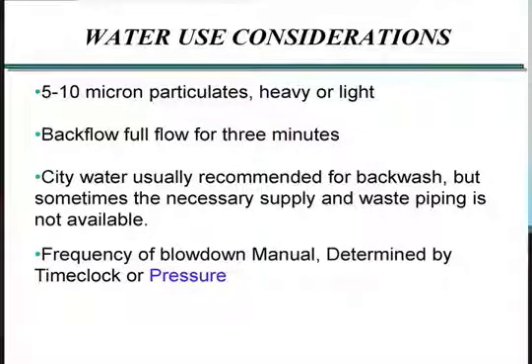Usually we'd recommend city water for this because of the fact you're taking so much water out of the system. The problem with that is sometimes you don't have the waste piping size, or if you're doing metering on the discharge of it, that might be a pretty large size meter. So sometimes people will use the process water, and this type of system can, more than other types, significantly affect the cycles of concentration.